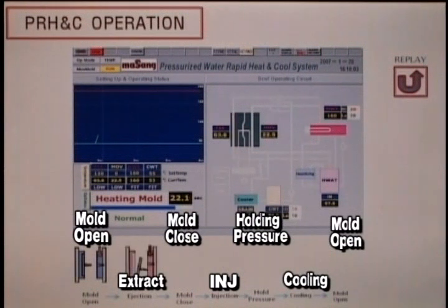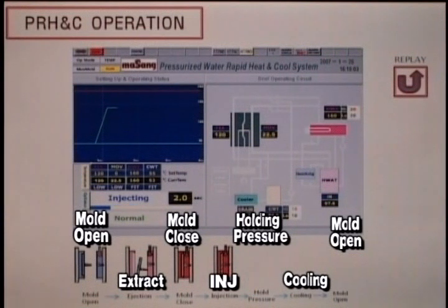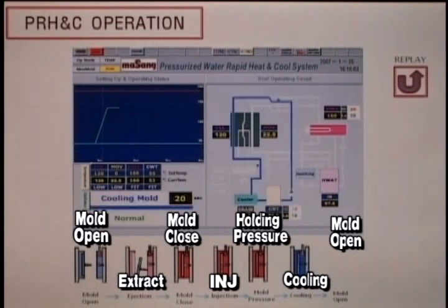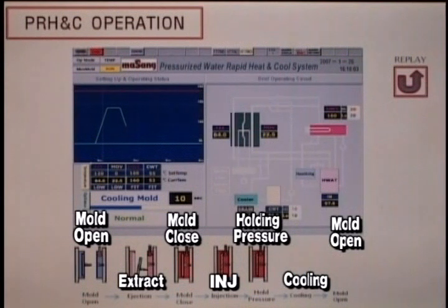One cycle of pressurized water rapid heat and cool equipment consists of mold heating, injection, removing the remainder of hot water, cooling, and removing the remainder of cool water. With mold open, the mold heating is started, and at the time that the set temperature is reached, the mold is closed. During the set time, injection is going on, and after injection is over, the remainder of hot water is drawn back for cooling. After the cooling process is over, the mold is open. With removing the remainder of cool water, heating is processed again.